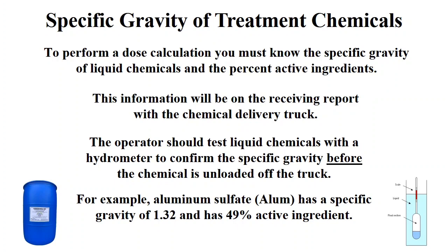Alum is a coagulant and helps remove the turbidity from the water. The specific gravity of 1.32 means that alum is 32% heavier than water. Alum is 49% aluminum sulfate. It is important to know the active ingredient, since only 49% of the alum you feed at your plant will coagulate the water.